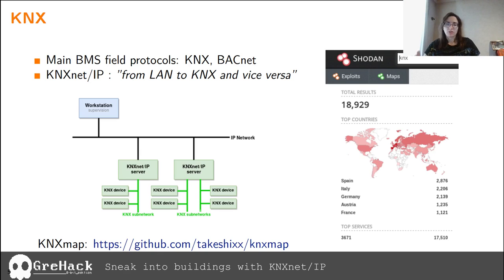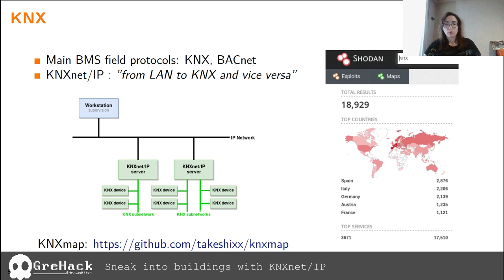As you can see in this typical example of network architecture from the KNX specification, it requires a gateway between the IP network and the fieldbus, referred to as a KNXnet/IP server in the standard. Typically, when we want to send a configuration change to a device from the workstation, a KNXnet/IP frame will be sent to the server, which translates it to a KNX frame to transmit to targeted devices using a KNX-specific address topology.